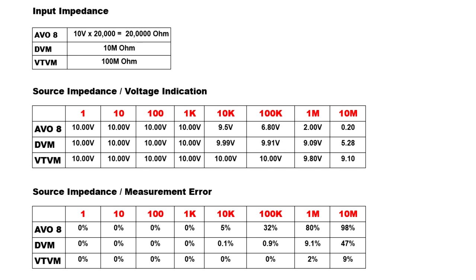Well, looking at the table, you can see that all 3 of our meters actually compared very well with each other and measured correctly up to a source impedance of 1 kilo ohm. But as the source impedance increased beyond 1 kilo ohm, you can certainly see for the AVO 8 and the DVM, the actual meter reading seemed to diverge away from the true measurement, which should have been 10 volts.